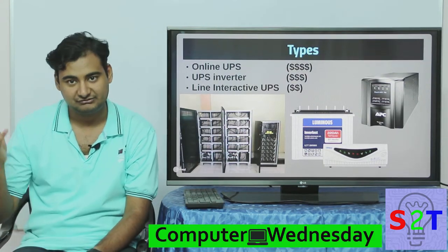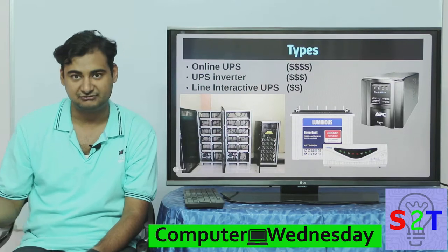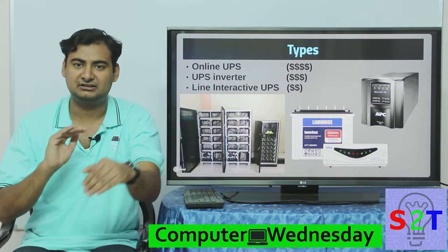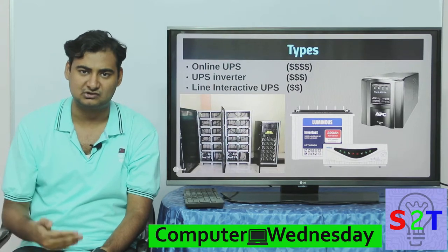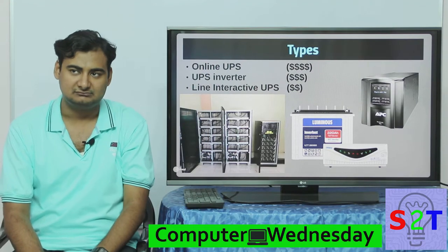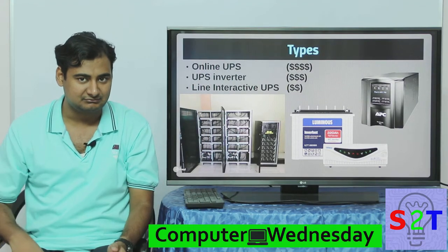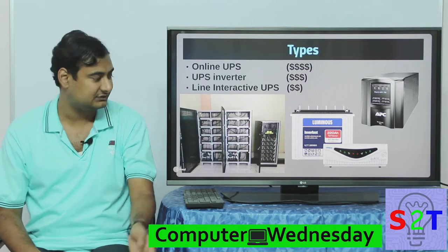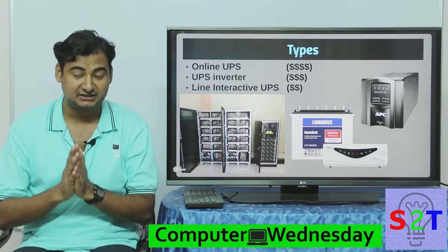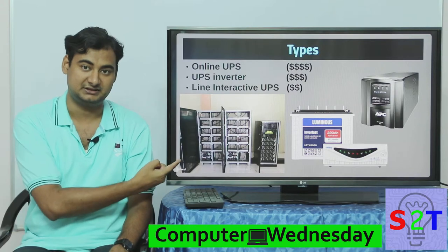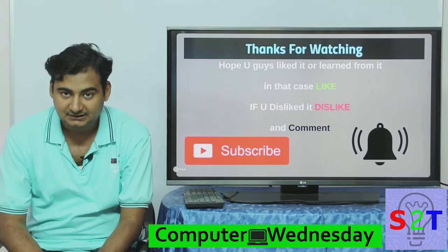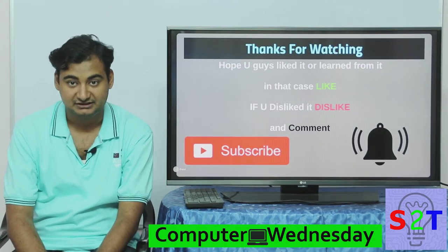The cheapest type is the line interactive UPS. It has a built-in stabilizer — so if you have over-voltage, it will control it, and if you have under-voltage, it will boost it. If you have good power conditions with no voltage drops or spikes, this will serve you fine. If your power is generally good but blackouts can last two to three hours, this type can get you by. However, if you are running very critical operations, you'll want to employ a higher-tier UPS regardless of power quality.